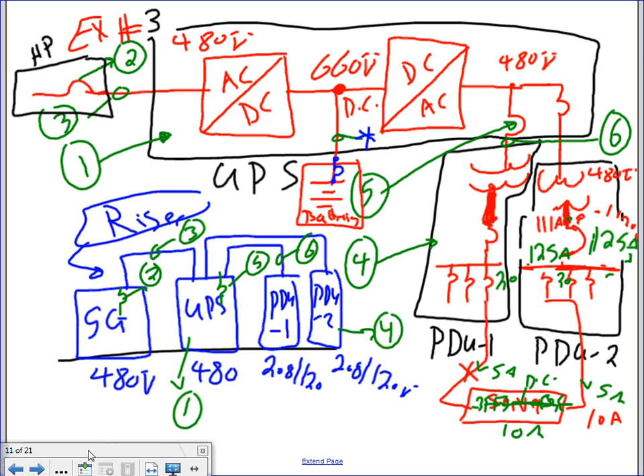Okay, so I know this is busy, guys, but you did the riser math. When you did your riser, remember that we took a feeder from the switch gear to feed something called a UPS system. And from that UPS system, I think we have two UPSs, right? This time we had two UPSs. This example has one UPS, and we're feeding two PDUs.